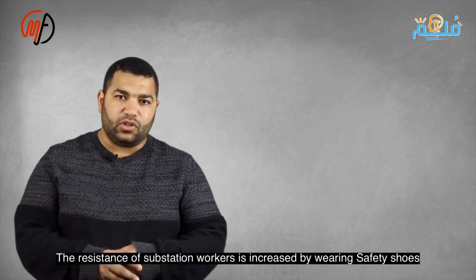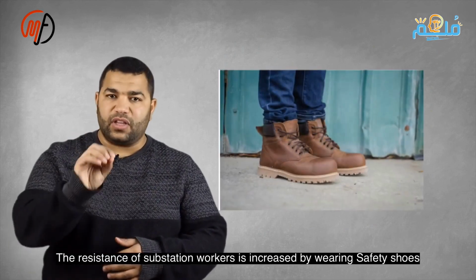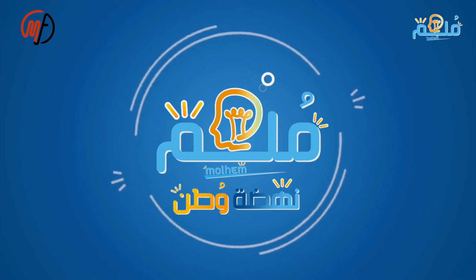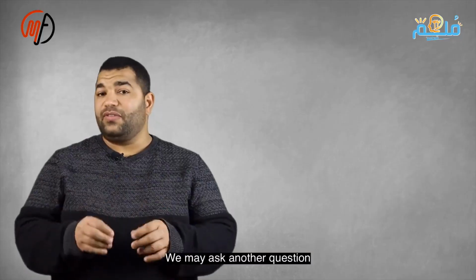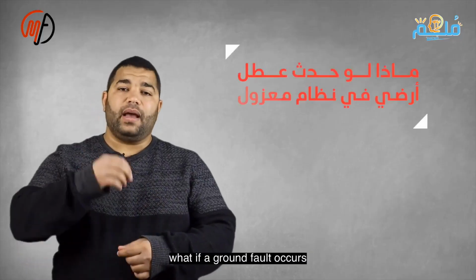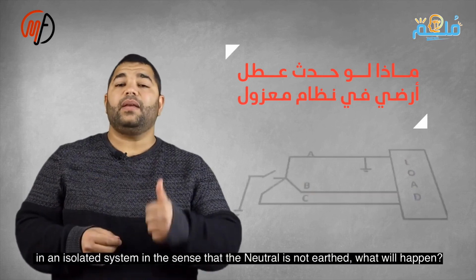What if a ground fault occurs in an isolated system with ungrounded neutral? How will fault current flow in a system not connected to ground? Theoretically, no fault current flows as the circuit is open. In reality, fault current returns via stray capacitance of transmission lines, but is smaller than if the system were grounded.